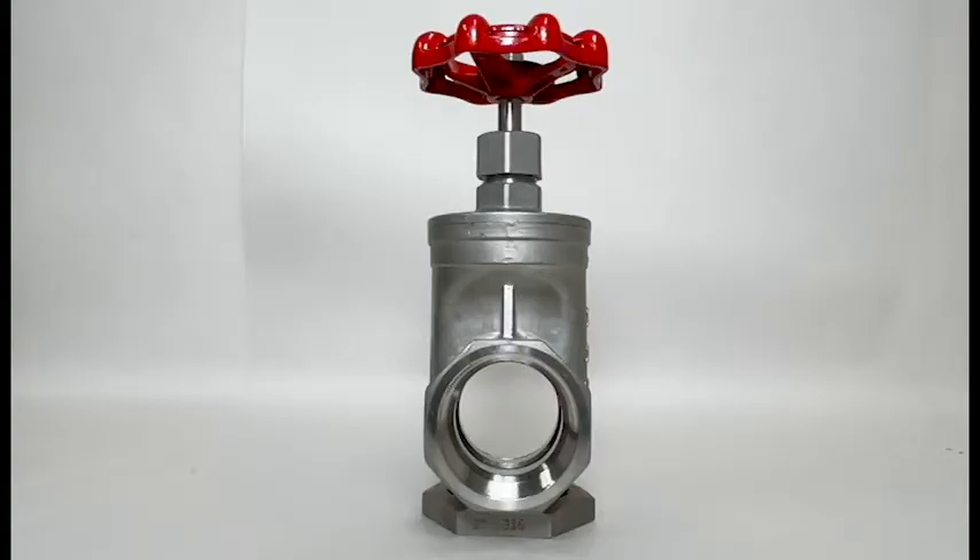Gate valves are often used when minimum pressure loss in the flow path is needed. When fully open, a typical gate valve has no obstruction in the flow path, resulting in very low pressure loss, and this design makes it possible to use a pipe cleaning pig. A gate valve is a multi-turn valve, meaning operation is done by means of a threaded stem. As the valve must turn multiple times to go from open to closed position, the slow operation also prevents water hammer effects.